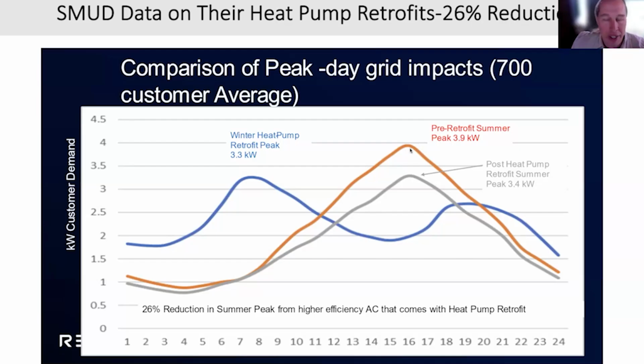Their peak was with a normal air conditioner, minimum efficiency. None of these 700 homes had fancy air conditioners, and so the peak was at 3.9 kW. They put in heat pumps, which automatically come with a computer in them, raising the efficiency of the air conditioning roughly 50% or more. That meant the peak dropped in the summertime to 3.4 kW among these 700 homes.